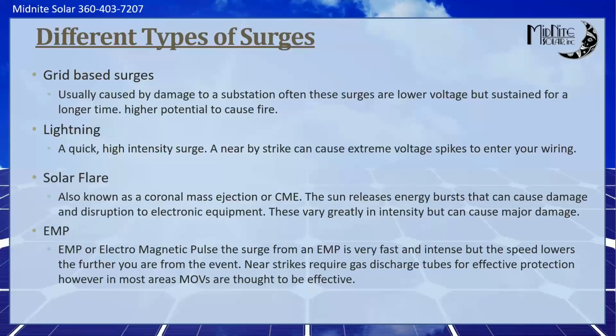A lot of people think that, hey, if I don't take a direct strike, it's not a problem. But you can get a lot of induced voltage by a nearby strike. Lightning can strike quite a ways away, actually, and you'll get some pretty incredible induced voltage. I've always wanted to run an experiment where I take like 100 feet of 12-2 Romex and twist all 3 wires together on one end and put an oscilloscope or something on the other end so I can catch it quick enough during a lightning storm, but I haven't quite been brave enough. It would be really interesting to see what there is there, but there is a lot of induced voltage in wire. It makes a great antenna.